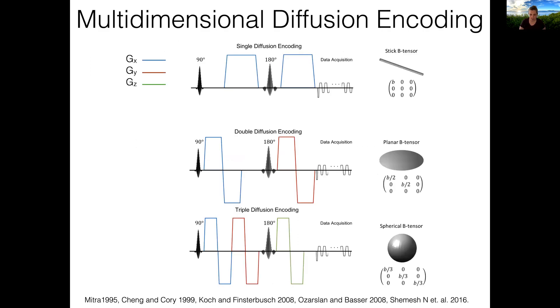Multidimensional diffusion encoding refers to a pulse sequence that encodes more than one diffusion orientation before the readout. In this way, we can encode planar or isotropic diffusion with two or three pairs of orthogonal gradients. Instead of a b-vector, the diffusion sensitivity of these sequences can now be characterized by a b-tensor.